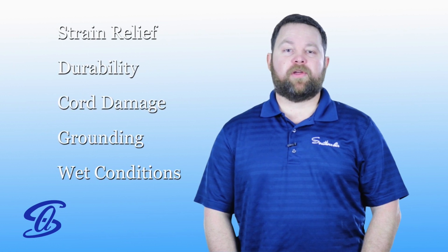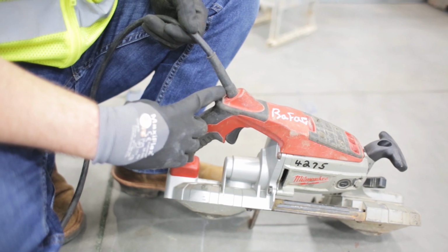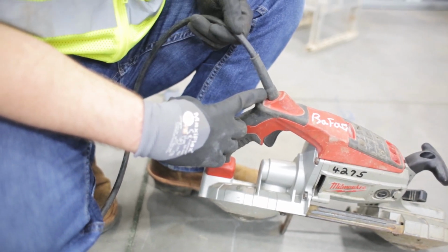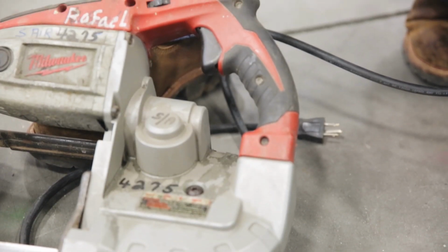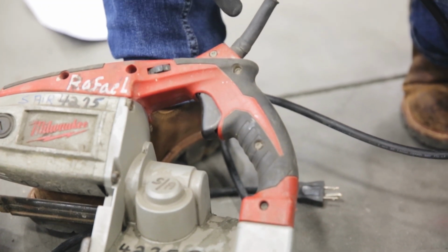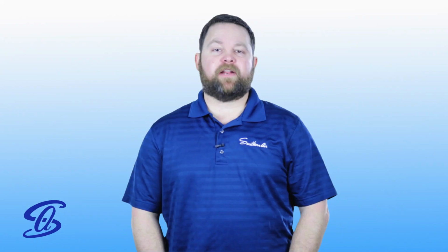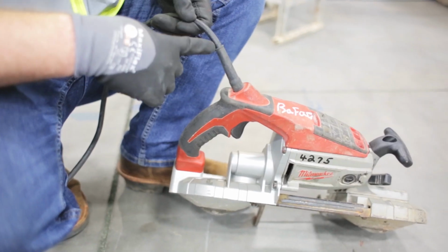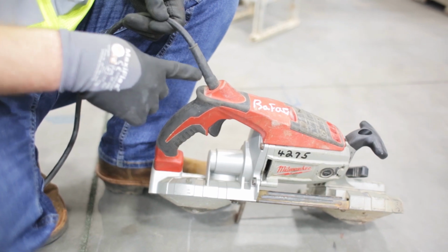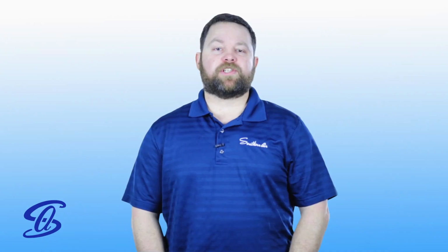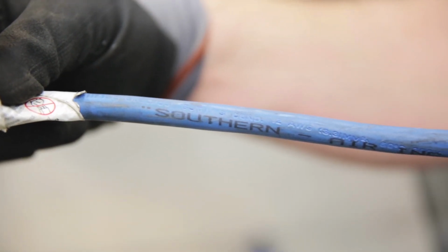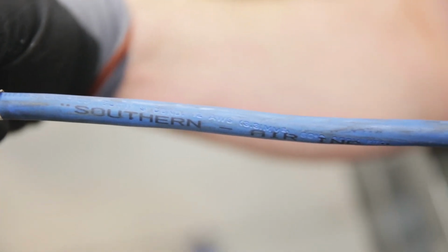The 5 areas we're going to focus on are strain relief, durability, cord damage, grounding, and wet conditions. To reduce the strain on cords, flexible cords must connect to devices and to fittings in ways that prevent tension at joints and terminal screws. Flexible cords are finely stranded for flexibility, so straining a cord can cause the strands of one conductor to loosen from under terminal screws and touch another conductor. OSHA requires flexible cords to be rated for hard or extra hard usage. Usage ratings are required to be marked along the length of the cord, as you can see here.